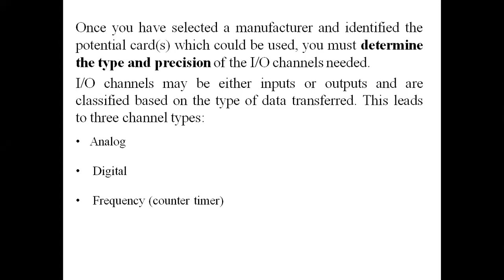What about the precision of the IO channel? It pertains to the accuracy and transient characteristics of the D to A and A to D converter employed. The accuracy of the converter is a function of bit length. Most converters will have 12-bit resolution, which is ample for most applications. However, this depends on the application and should be a consideration prior to purchasing.